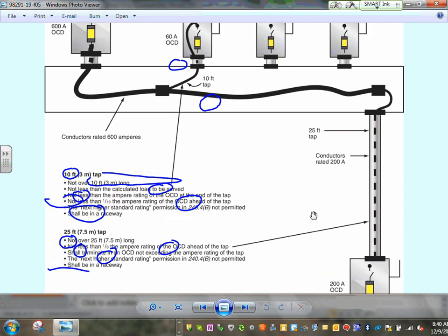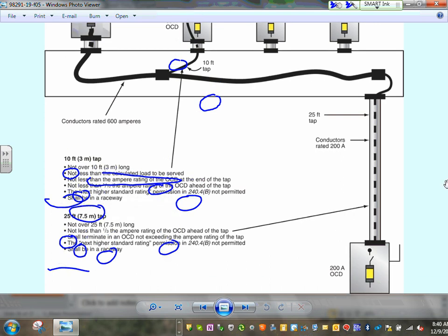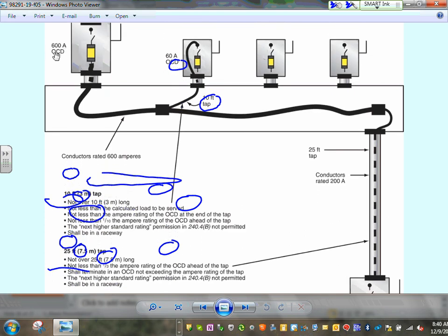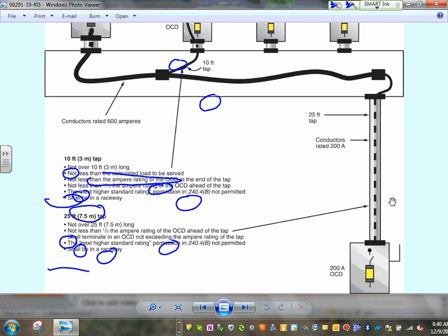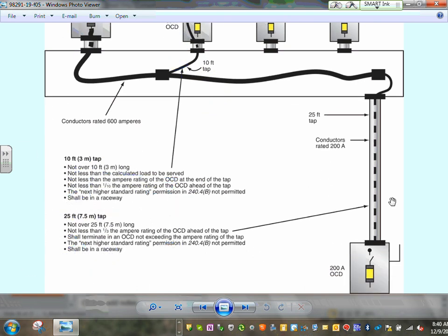The first thing, when you have a 25-foot rule, when they tap: remember, the overcurrent device right here, how much is it? The overcurrent device is 600. So when you have a 600 and you need to tap a feeder, 25 feet, you take 1/3 of 600, gentlemen. What would that give you? 200. So this conductor here has to be 200 amp, the smallest conductor. It can't be 150 amp. So go to 310.15(B)(16) and find me a conductor for 200 amp.